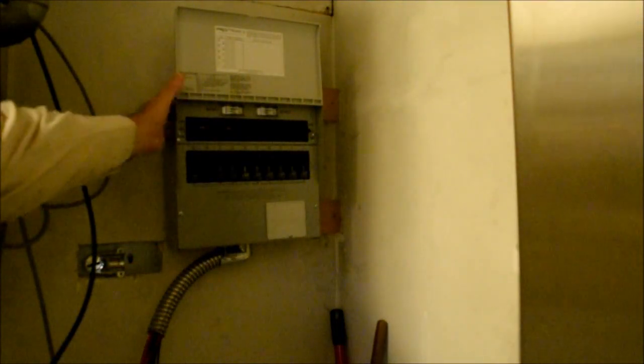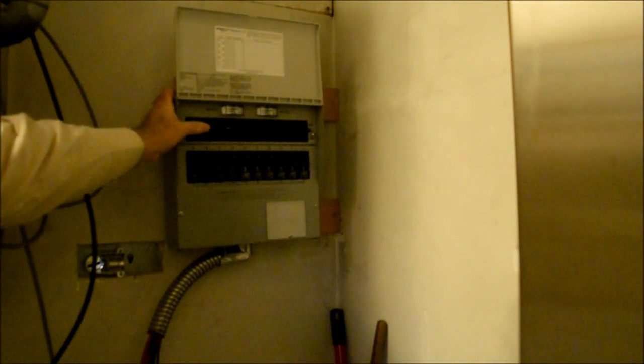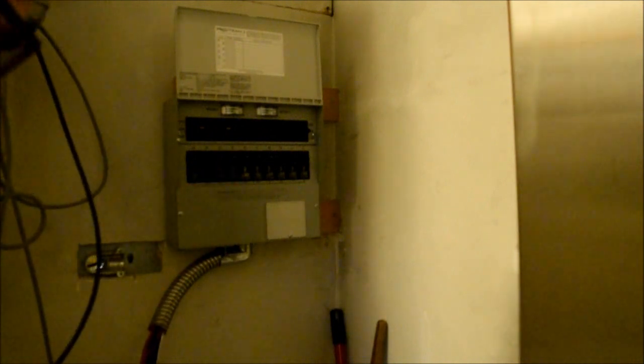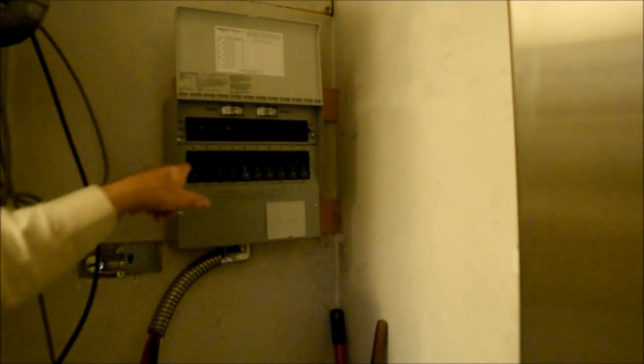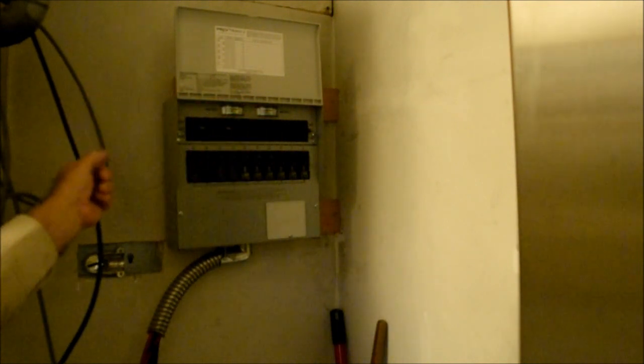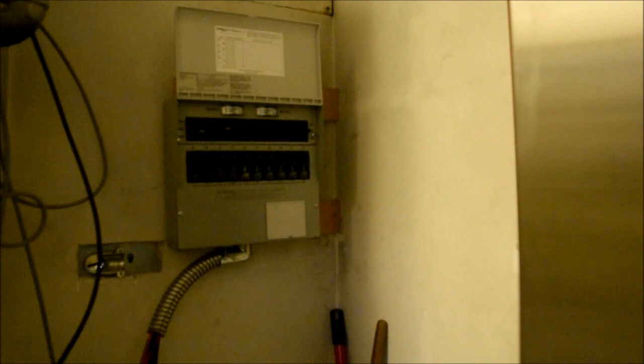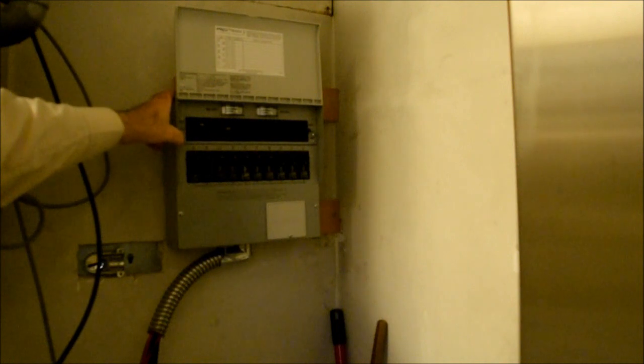Okay, this is the transfer switch. You see, it's not just a single switch. It's actually ten switches. And what we've got here is a set of circuit breakers and then a set of switches. And wires come out of here that go into the panel. Basically what you do is you disconnect a circuit from the circuit breaker in the panel, it's routed through the transfer switch and back to the circuit breaker. And depending on the position of these switches up here, you can either be getting power from your auxiliary power or getting power from the grid.